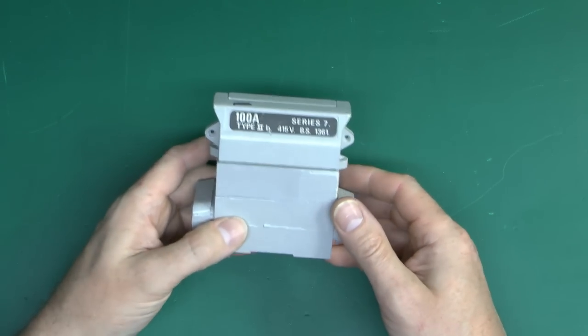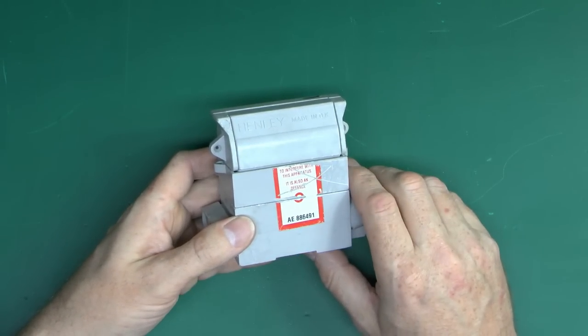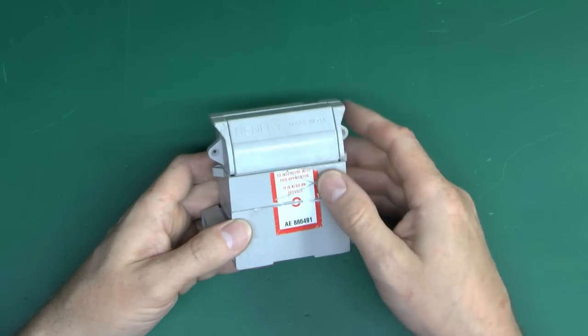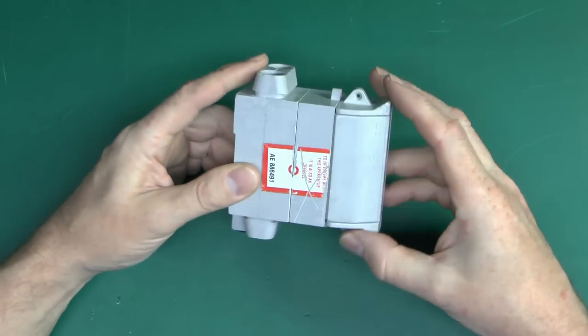Now these come in a variety of styles. This one happens to be a Series 7 made by Henley as it says there, made in the UK. They normally have labels on this saying do not interfere with this apparatus, this is an offence, because as I said earlier these don't generally belong to the owner of the building or whatever. These belong to the network operator.